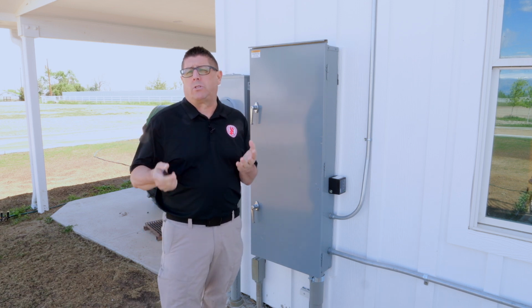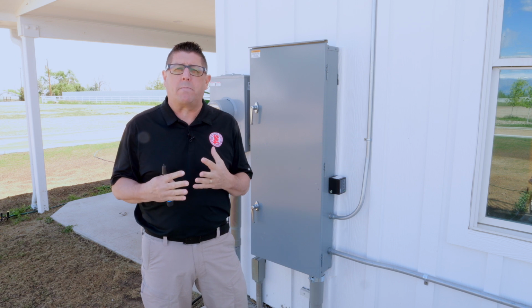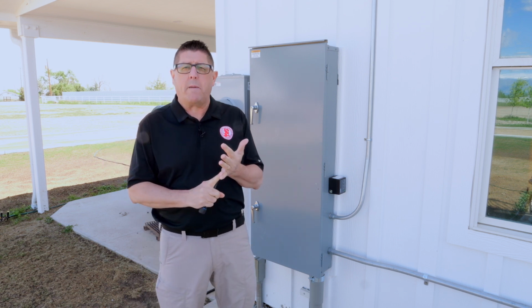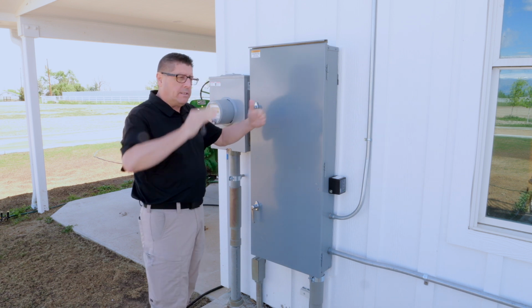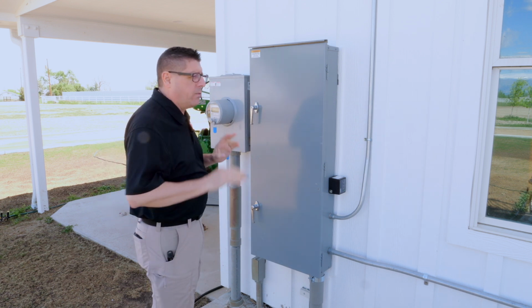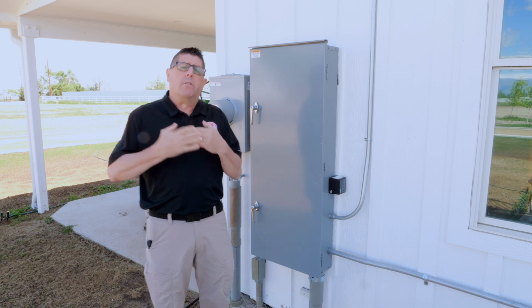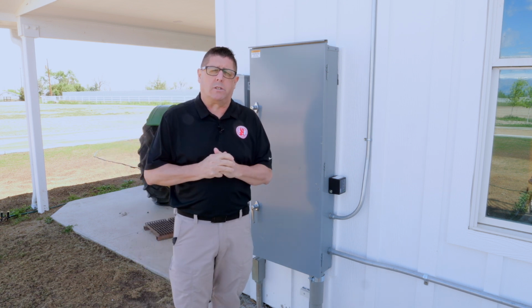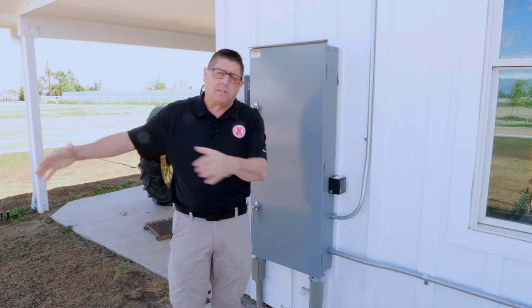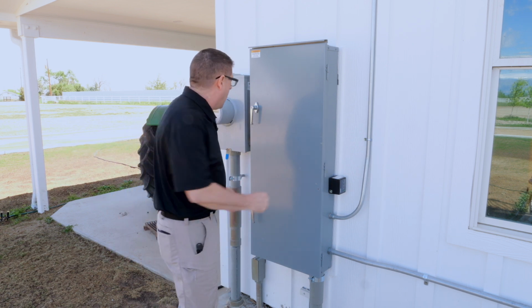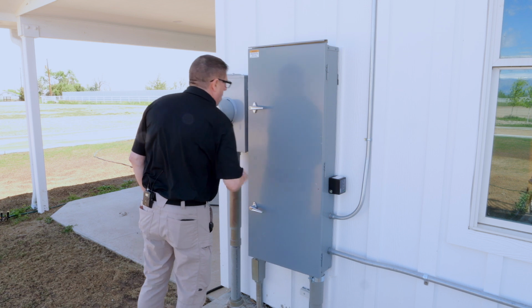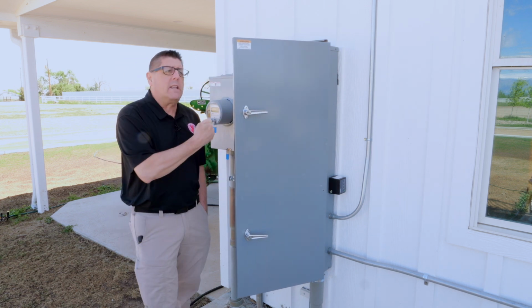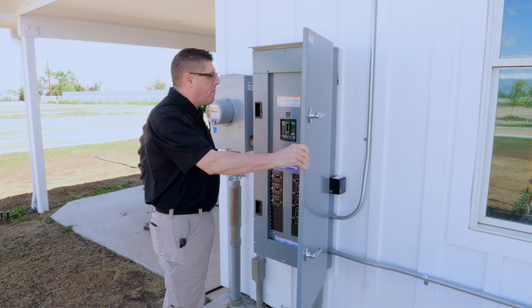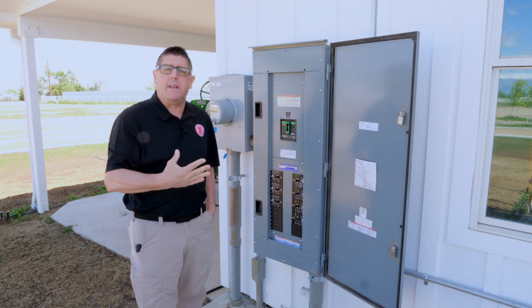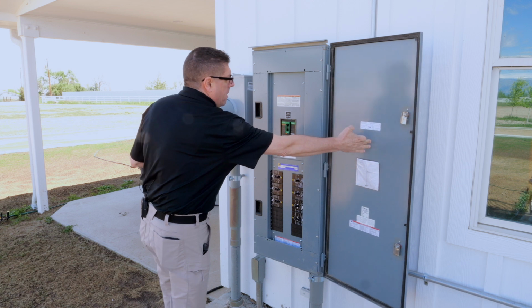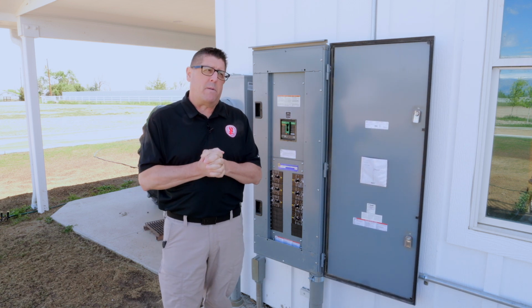Now, if you remember certain rules when doing any type of inspection, first rule, working space. That's 30, 36, 78. That's our working space for any piece of equipment at a minimum. The larger our voltage, the wider our space needs to be, and what's behind us. Since we are outside, I don't worry about what's behind me, and so now I can open up these panels. When you're inspecting a panel like this, the door has to open up to at least 90 degrees, if not wider. This opens up to a complete 180. We can open this up safely.